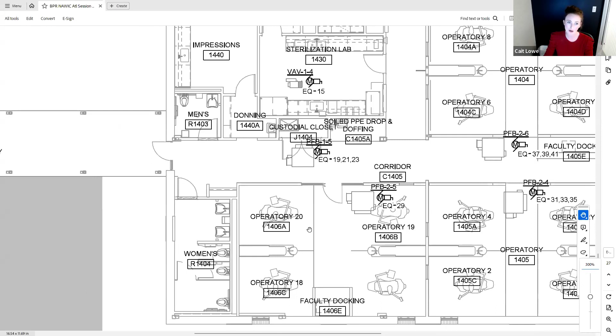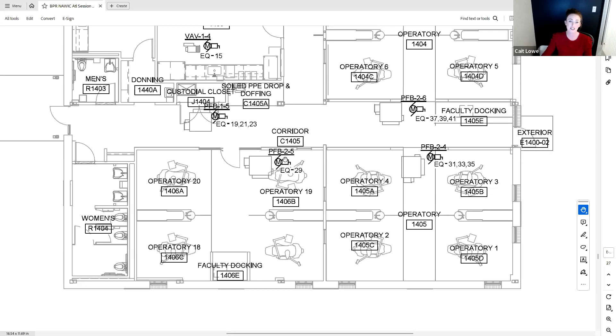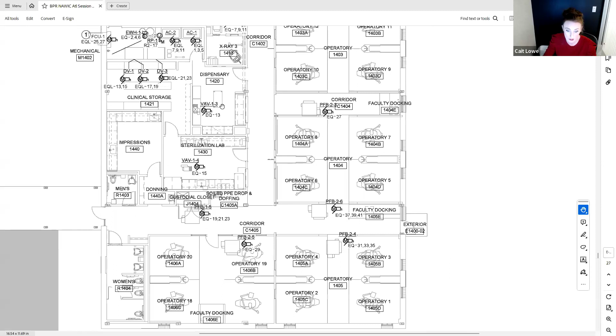Next you're going to see is your equipment. Equipment is different than your power. Equipment is supplied by others, like our mechanical contractor, but we have to do that termination, we have to make it function. So we have to do the wiring in the conduit plus a device or a switch, which we usually call disconnects, where it literally has to turn on and you physically can turn it on or off from one point. But that does not mean it's not necessarily provided by the HVAC contractor, so you've got to check your notes.